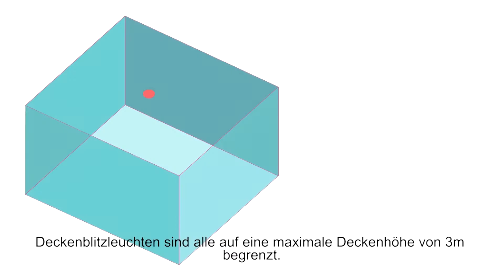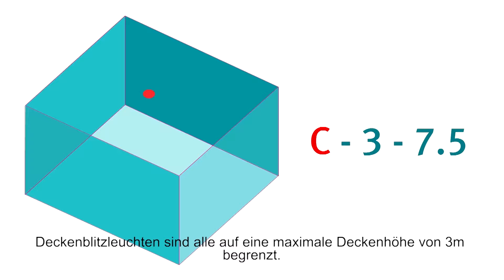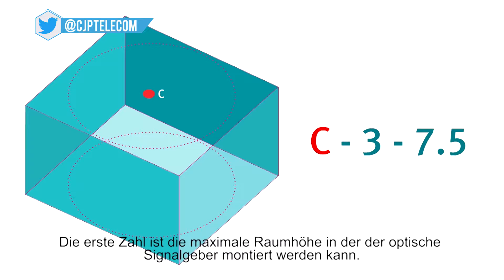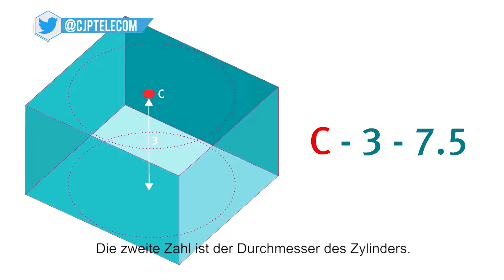A ceiling mounted VAD might be rated as C3 7.5, where C stands for ceiling. The two numbers represent the coverage volume in the shape of a cylinder, where the first number is the maximum ceiling height the VAD can be mounted and the second number is the diameter of the coverage.